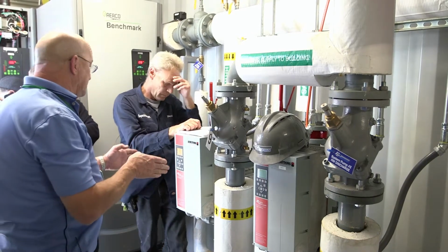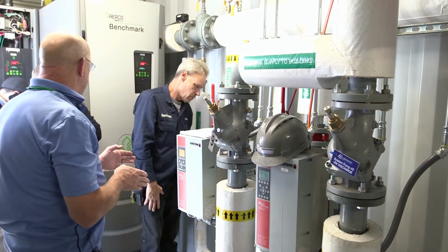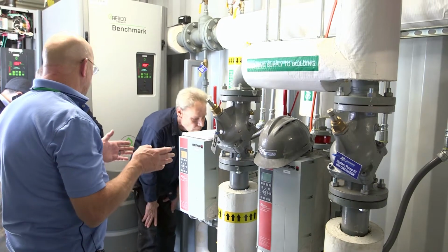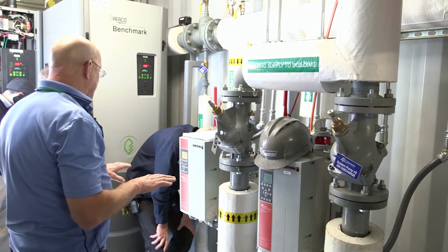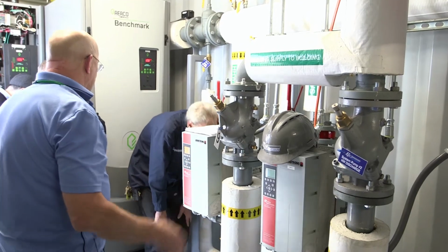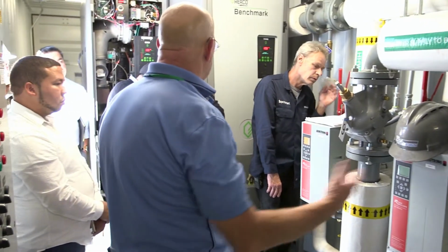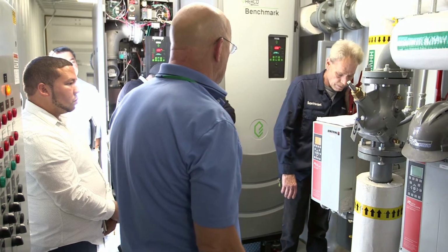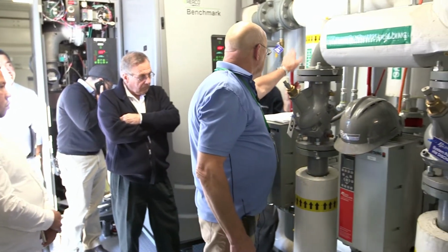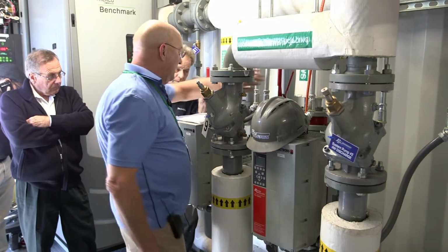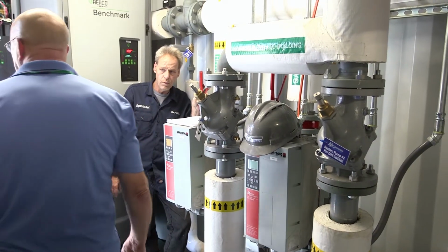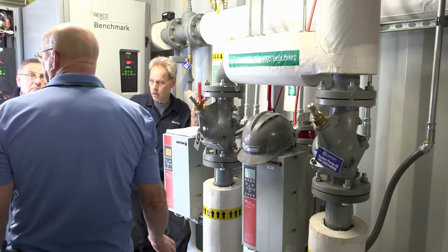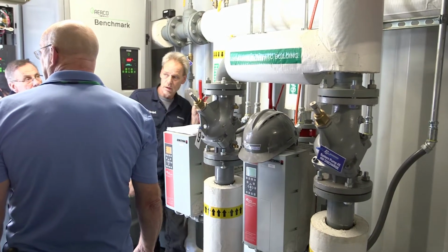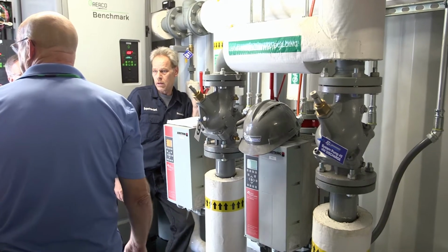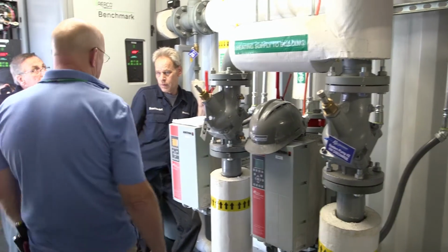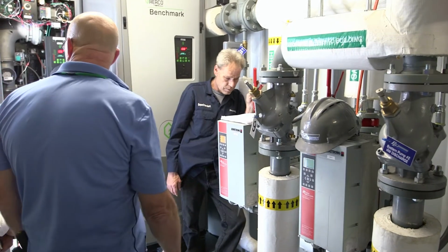There's always going to be a difference in pressure from one side of the pump to the other. That's called your head pressure. That way you'll know the pump is moving the water. If you have equal pressure on each side of the pump, you have no head pressure, there's something wrong with the impeller in the pump, and you want to switch over to the other pump. Again, one here, one here. What is that pressure typically in the loop? The inlet pressure will be whatever the system pressure is, and the outlet pressure will be about 10 to 15 pounds higher, because it's the differential of the moving of the water.